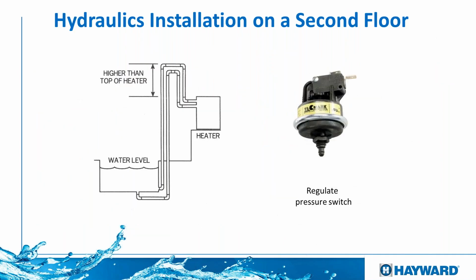If we want to install these heaters, and this goes for gas heaters also, either above or below water level, it is going to be recommended to adjust the water pressure switch. Now, the water pressure switch is internal. It's inside of the heater, and this switch will allow us to adjust the pressure from 1 to 10 psi.